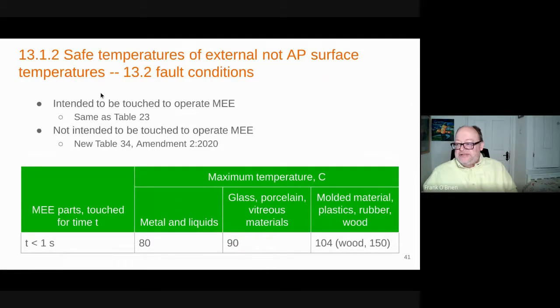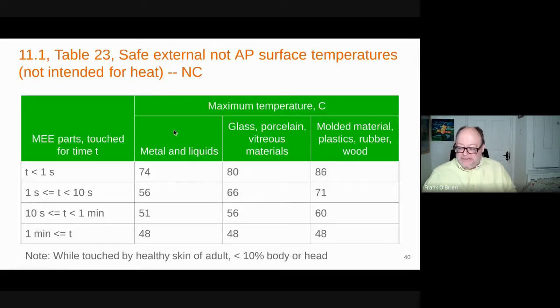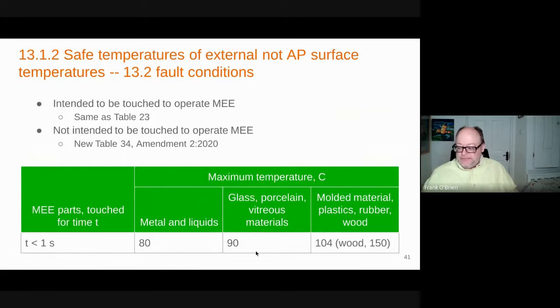Safe temperatures in single fault on a surface. This is new. This is Amendment 2. So if you're up to Amendment 1, 2012, which is what we're using now, this table doesn't exist, and you have to meet this table, although there is some kind of guidance. What do they call them? Interpretation sheet, and this is an IEC interpretation sheet that says, I don't know, 105 if your risk management allows it. And then this says less than that.